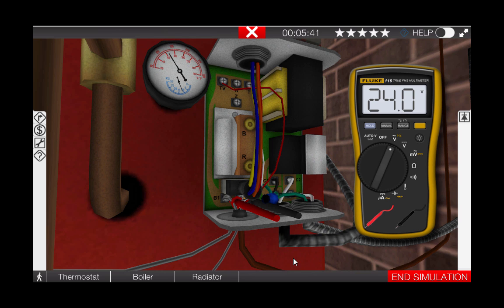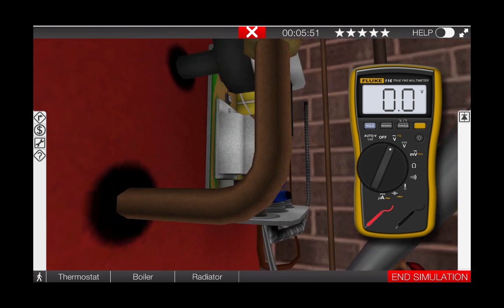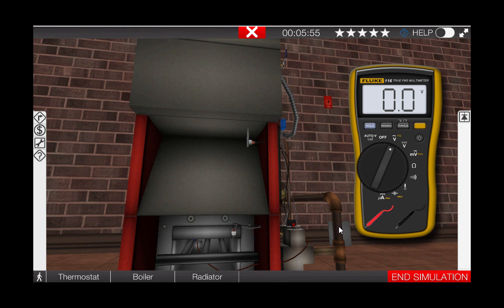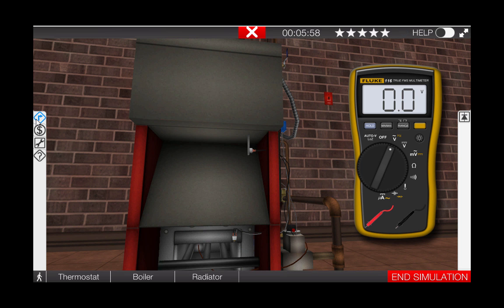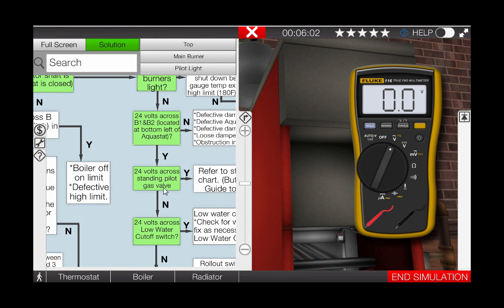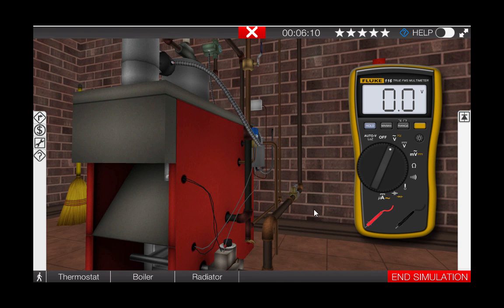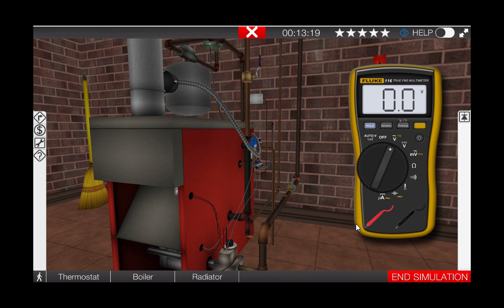Our next step is to check the safety switches in the circuit. Store the meter leads back at the meter temporarily by clicking on them. Going back to the troubleshooting flowchart, our next step is to see if we have power at the gas valve. This can be done by locating the gas valve on the side of the boiler, clicking on the meter leads, and placing them on the glowing hotspots at the gas valve. We can see that there is no voltage present at the gas valve, and this is why the gas valve is not opening and sending fuel to the burners. Between the combination Aquastat B1 and B2 terminals and the gas valve, there are three important safety switches, and one of these switches is our culprit.